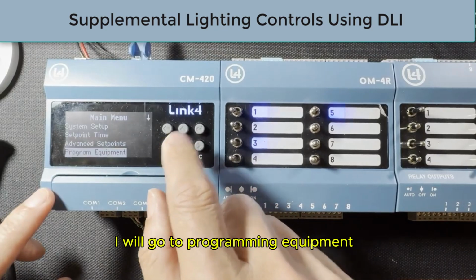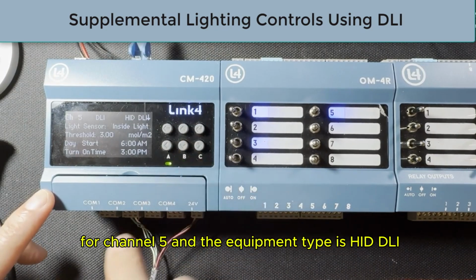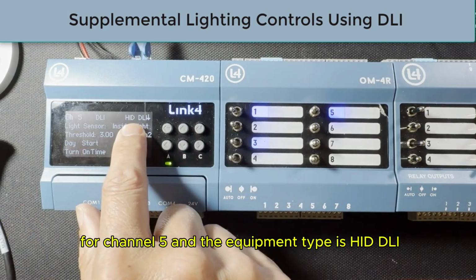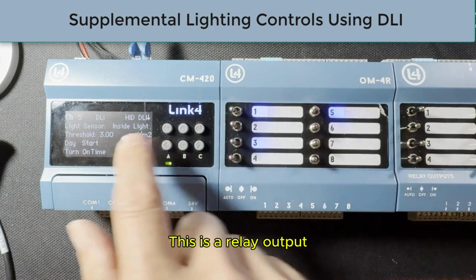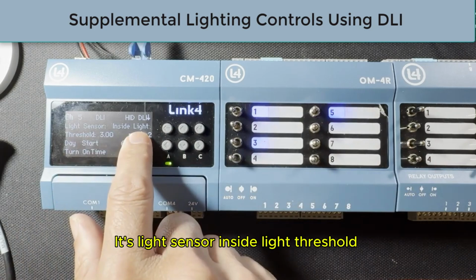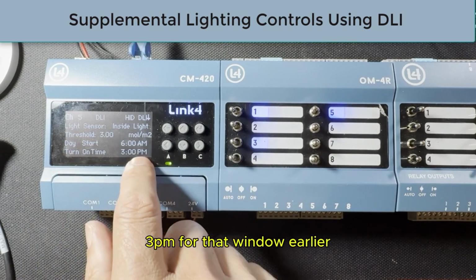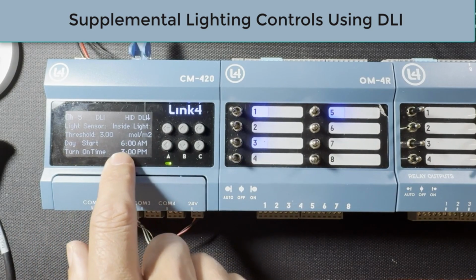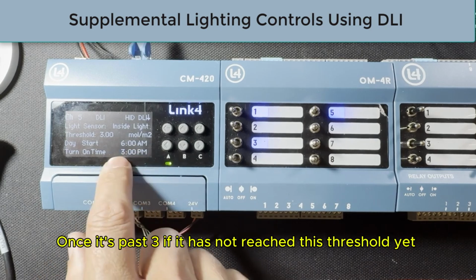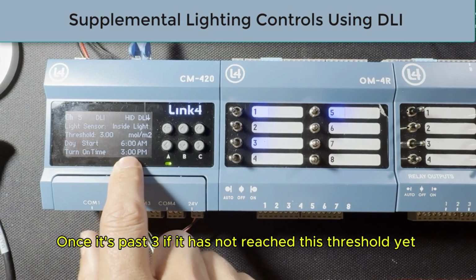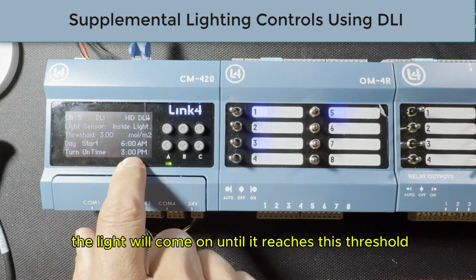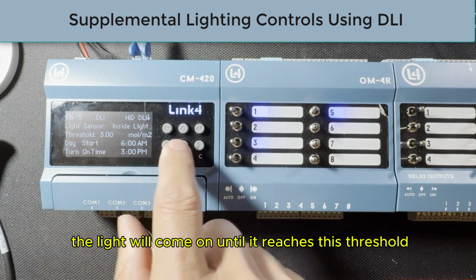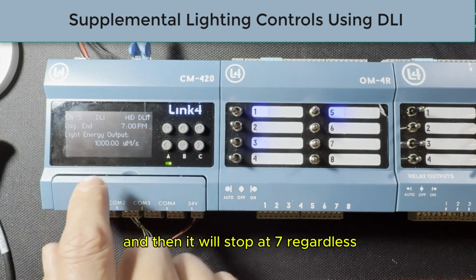I will go to programming equipment for channel 5. The equipment type is HID DLI. This is a relay output. Light sensor, inside light. Threshold, 6 a.m., 3 p.m. For that window earlier, it will start accumulating at 6. Once it's past 3, if it has not reached this threshold yet, the light will come on until it reaches this threshold. And then it will stop at 7 regardless.